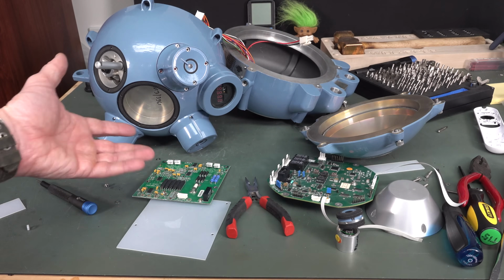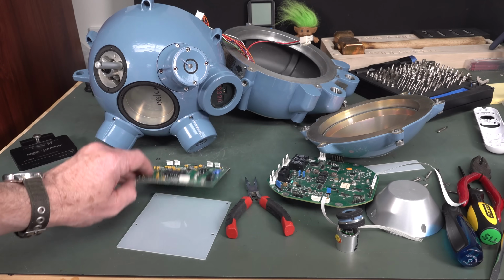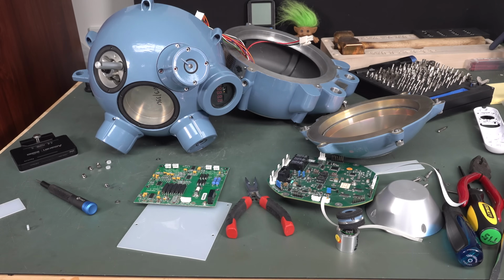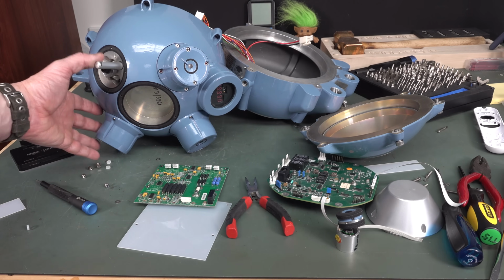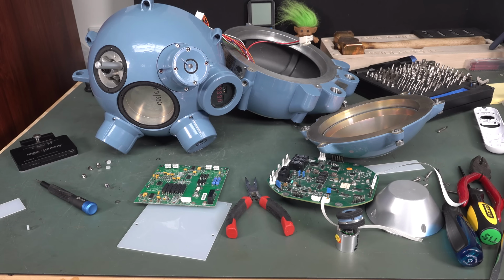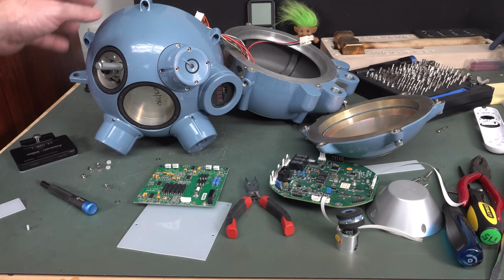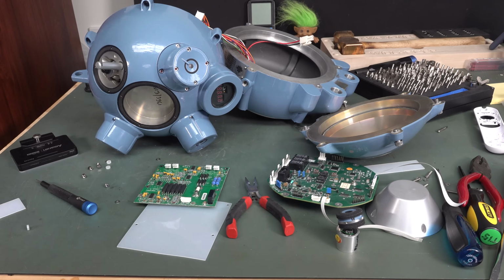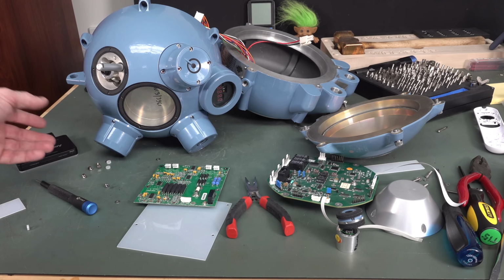It's designed so that if something goes wrong with any of this electronics - I don't know where that heater was, so it's obviously not inside this thing, and it can take significant amounts of power - and you get a spark from one of the connections and you've got a pressure leak, because you have to assume worst case scenario, and at the same time the electronics has failed, then you don't want the gas igniting in your factory and your whole factory going up. So these are intrinsically safe and pressure rated to the EXD standard. I won't pretend to know all the ins and outs of that, but it's an international standard for these sorts of contained devices so they don't ignite a flammable atmosphere.